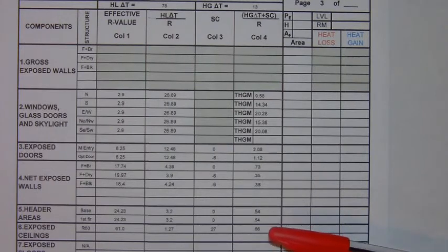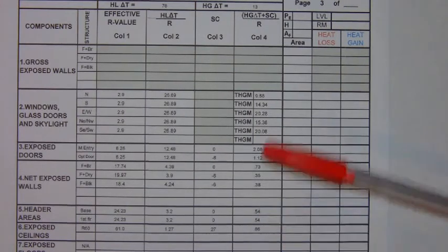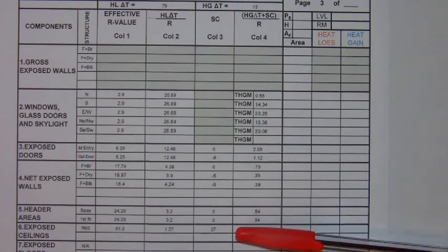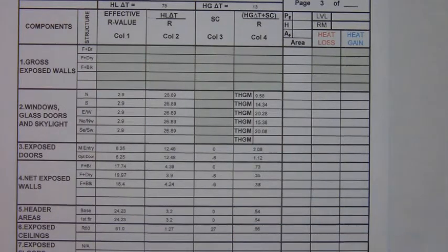And in many cases it will be much warmer in the attic than it is outside. In this case, we will solar correct on the positive side by adding 27 degrees to our temperature difference between the inside of the house and the temperature inside the attic space.